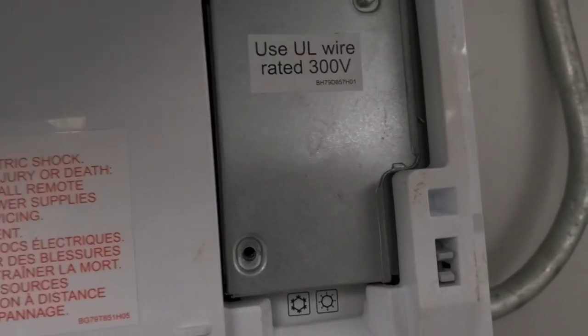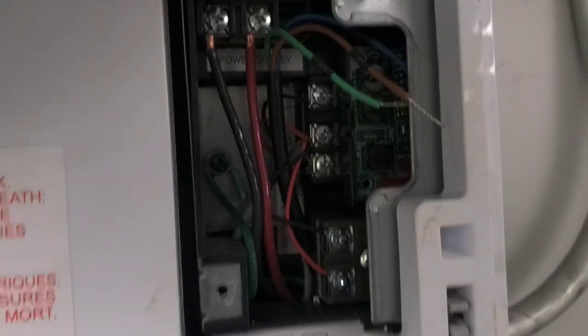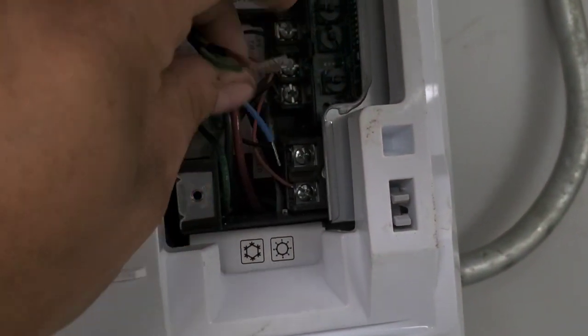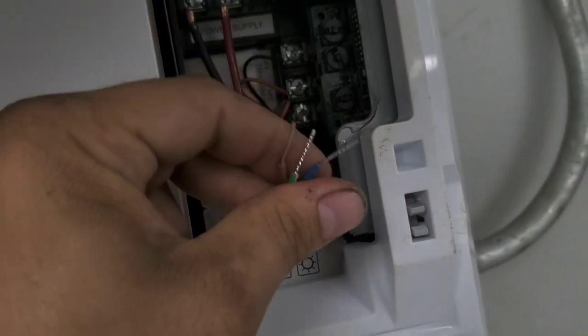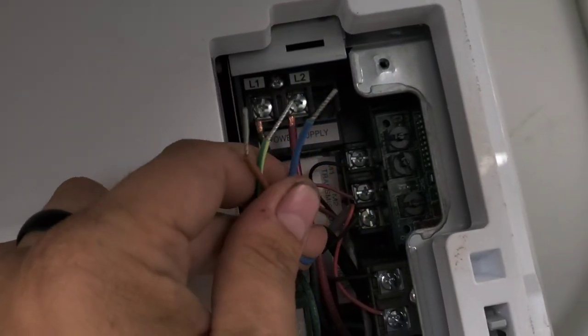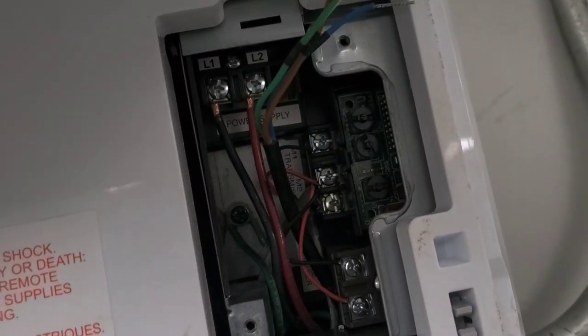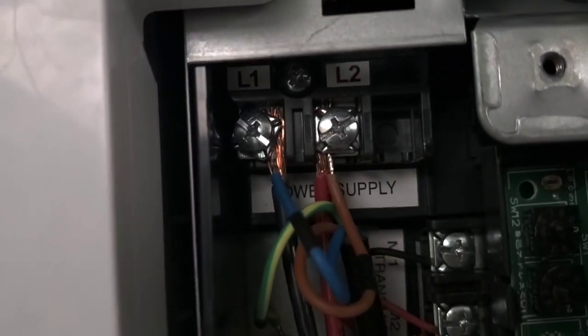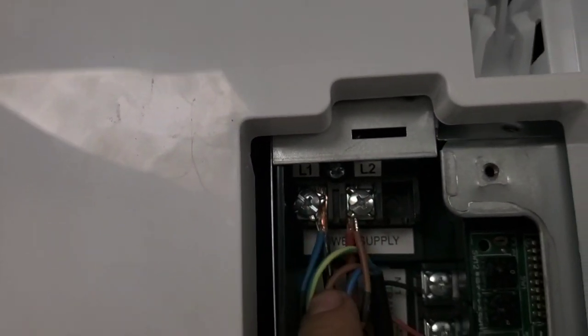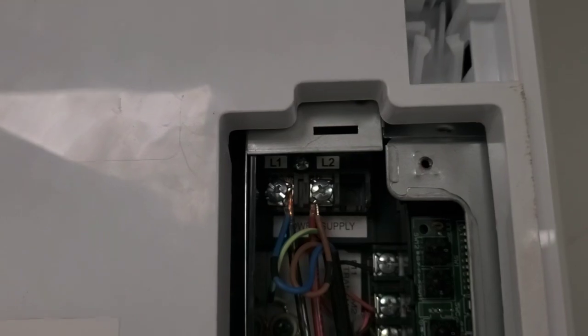First, we're going to make sure the wiring is hooked up properly, and that's not a very good sign. What do you know? He didn't hook up the condensate pump power connector. I've got to go through and connect the condensate pumps first, then I can turn these on. L1's terminal block broke tightening the screw. That's very common on a mini split. Their build quality is very poor.